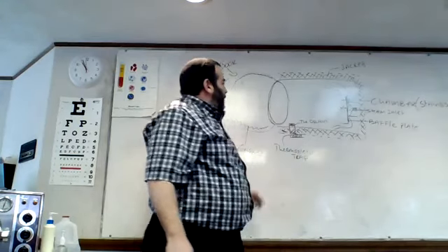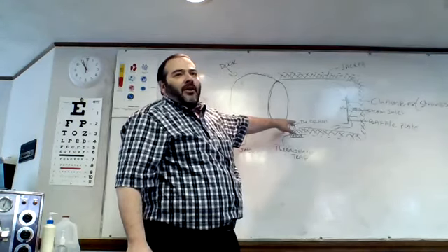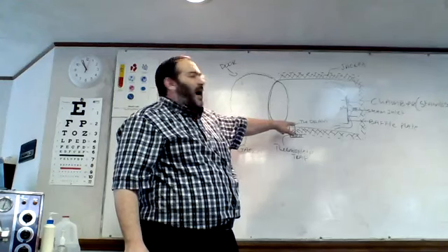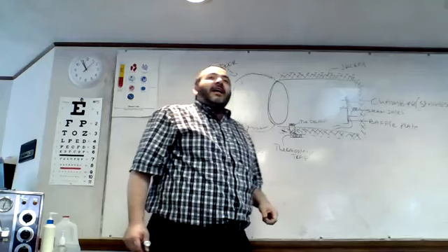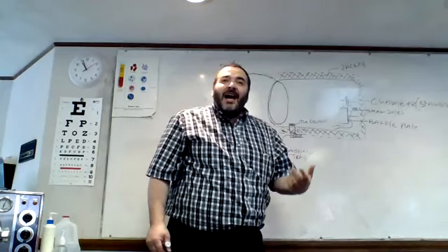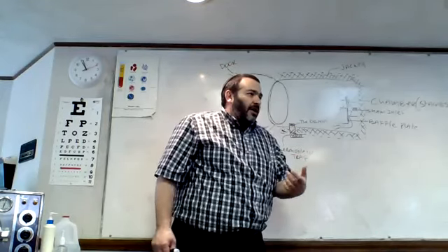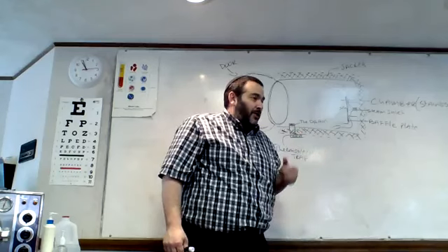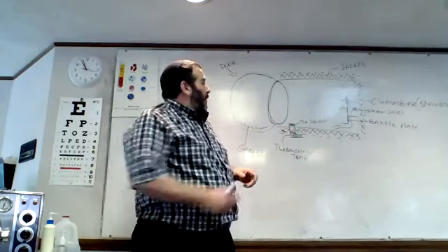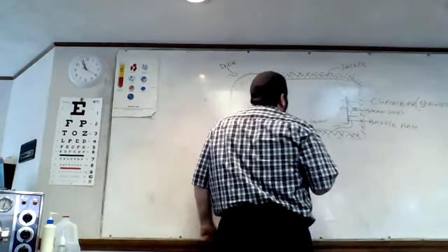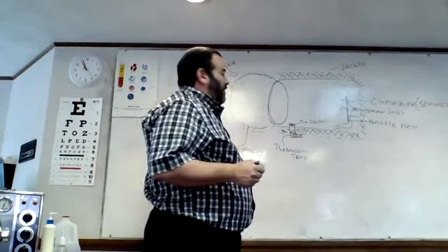The drain. The drain is customarily in the front bottom of the sterilizer. The drain is where the residual air and ultimately water, when steam condenses back to water, will drain into. Okay, so whatever has to come out will come out over here. So let me ask you a question.